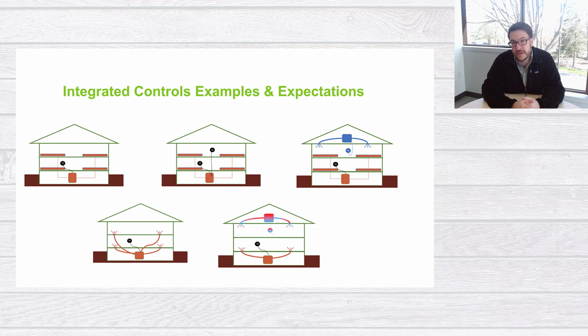If we now look at the home on the top right-hand side, we'll see that there's a central boiler heating the whole home and a central AC that's cooling the second floor. Let's say we were to swap out that central AC and put in a central heat pump. If it just has distribution to the second floor, it would not be a good candidate for integrated controls, because the first floor is still going to be calling for heat, the baseboards in that space are still going to be releasing heat, and the heat pump up in the attic would never have an opportunity to be running down to 30 degrees as the minimum.